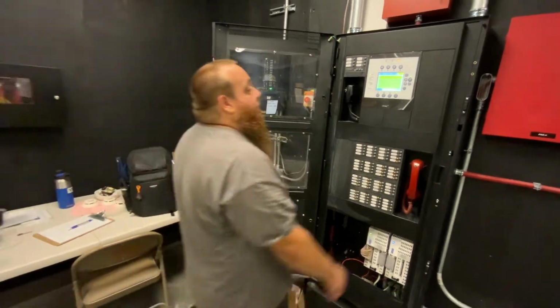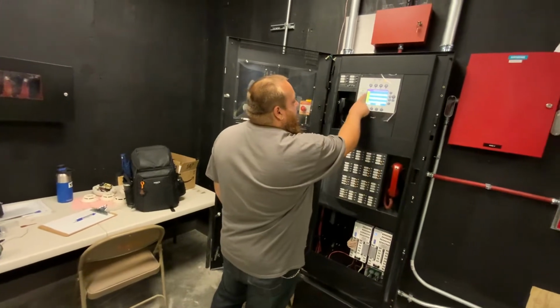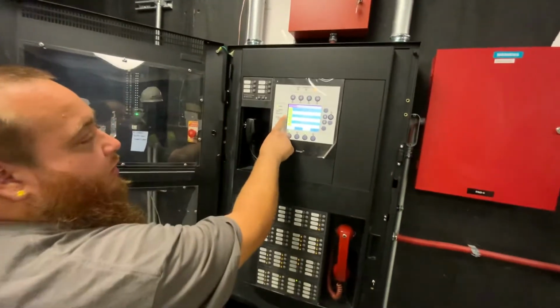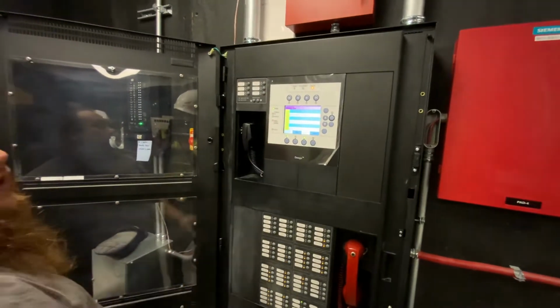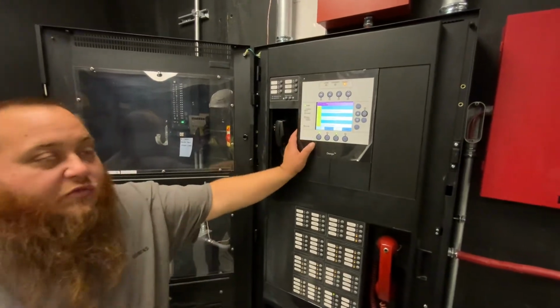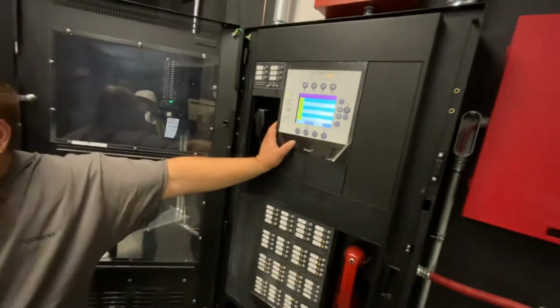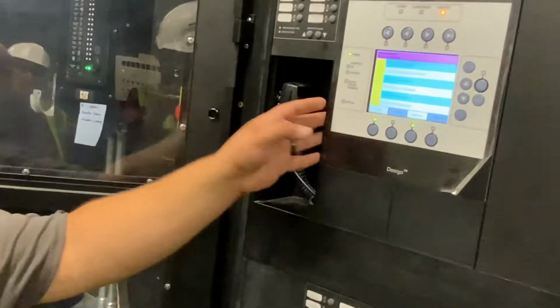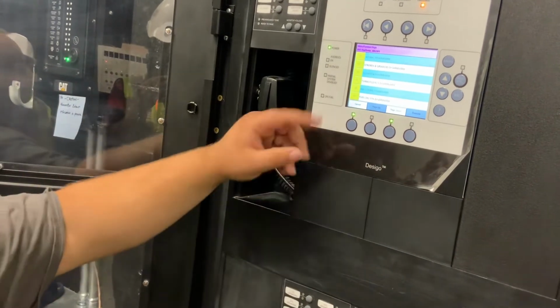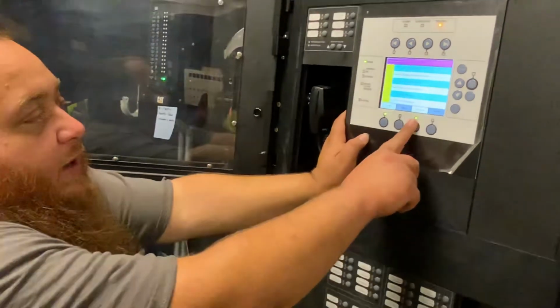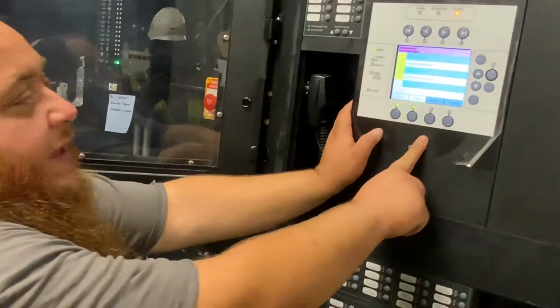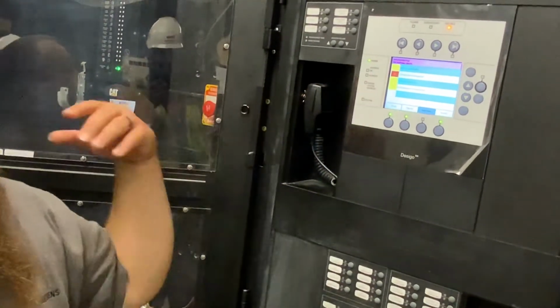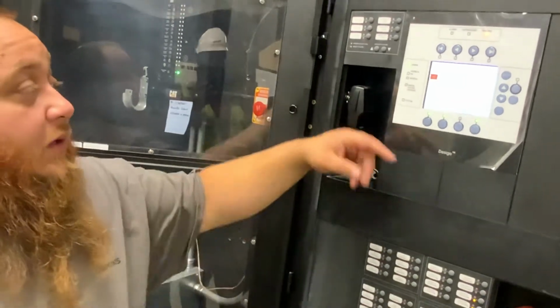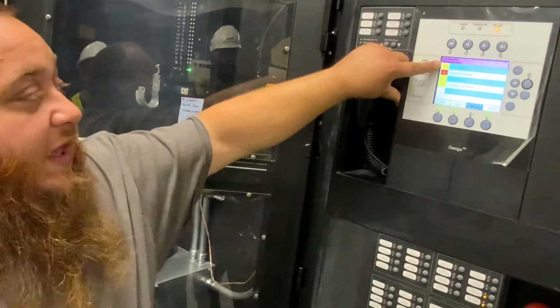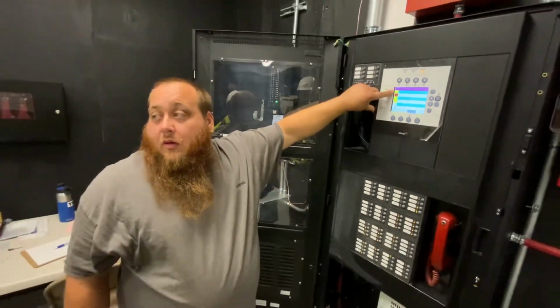We'll just go over your functions. You have your strobe disarm, speaker strobe disarm, elevator disarm, turnstiles, and your BAS connections - if there's any alarm here, the BAS system will know. Say we're testing the building, you don't want 100 alarm signals going to them, so you can disable that. This fuel signal you can disable too. Your HVAC - that covers all your dampers - and your HVAC shutdown would go to the BAS as well, covering all the physical shutdown, though we don't have that set up here yet.